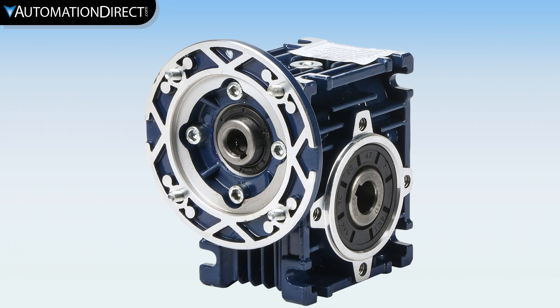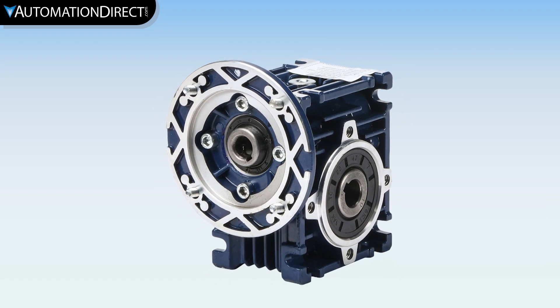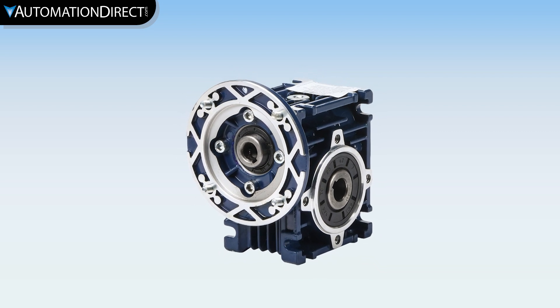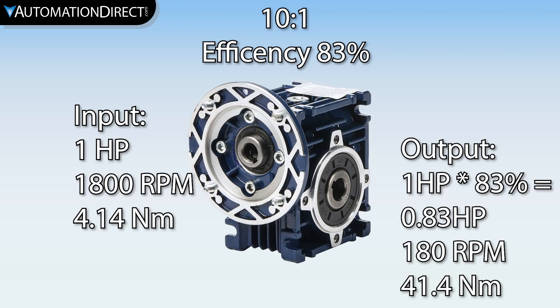A quick note if you're not familiar with gearboxes — also known as enclosed gear drives or speed reducers — these are mechanical drive components that reduce the drive's speed as well as increase the motor's torque by the gear ratio. For example, with a 10 to 1 ratio, the gearbox output is one-tenth of the motor speed and 10 times the motor's torque at approximately the same motor output horsepower, minus losses.